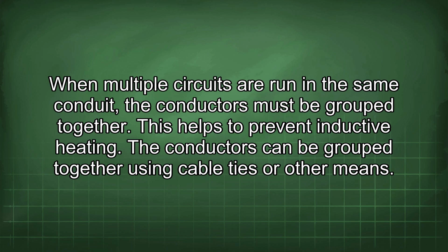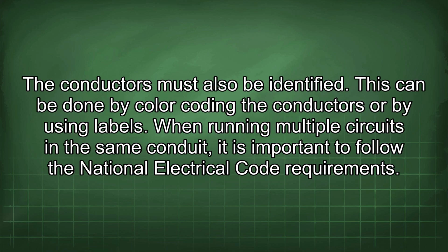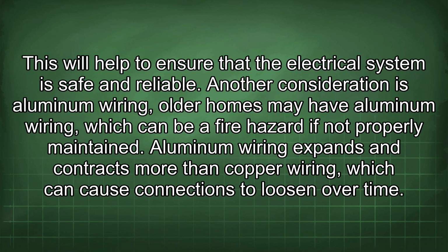When multiple circuits are run in the same conduit, the conductors must be grouped together. This helps to prevent inductive heating. The conductors can be grouped together using cable ties or other means. The conductors must also be identified. This can be done by color-coding the conductors or by using labels. When running multiple circuits in the same conduit, it is important to follow the National Electrical Code requirements. This will help to ensure that the electrical system is safe and reliable.